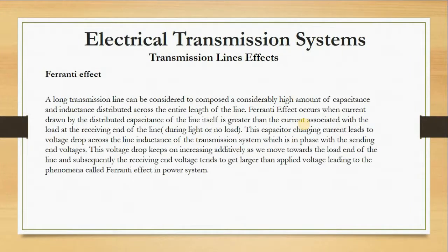He says that due to the voltage drops across the various impedances, by the time you put all of them together and arrive at the receiving end, you realize that the voltage at the receiving end is a little high. And usually this happens during light load or no load. That's the Ferranti effect for you.